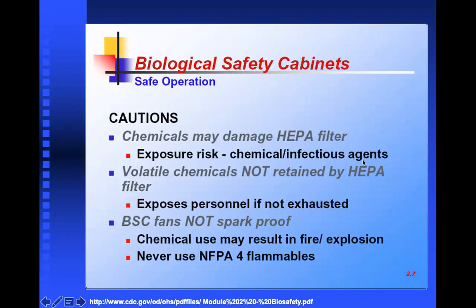Caution: chemicals may damage the HEPA filter. So all the chemicals you cannot use, they are too volatile compounds. In that case, you have to use another hood. Exposure risk, chemical or infectious agents, there is a risk. So if you do not wear gloves, or if there is a cut on your finger or hand or any injury, then it would be problematic. Volatile chemicals not retained by the HEPA filter expose personnel if not exhausted. Biosafety cabinet fans are not spark proof, so chemicals used may result in fire or explosion. Never use any NFPA.